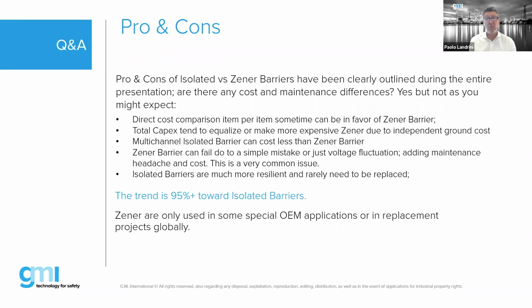Also, when you look at multiple channel isolated barriers, there are dual-channel, 4-channel, 8-channel barriers. In this case, the cost of an isolated barrier is much less than that of a Zener barrier, which is defined by standard—it cannot change, it's a fixed cost.